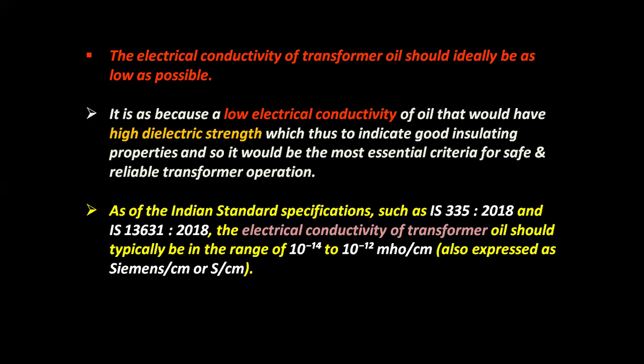As per the Indian standard specifications such as IS 335-2018 and IS 13631-2018, the electrical conductivity of transformer oil should typically be in the range of 10 to the power minus 14 to 10 to the power minus 12 mho per centimeter, which can also be expressed as Siemens per centimeter or S per centimeter.